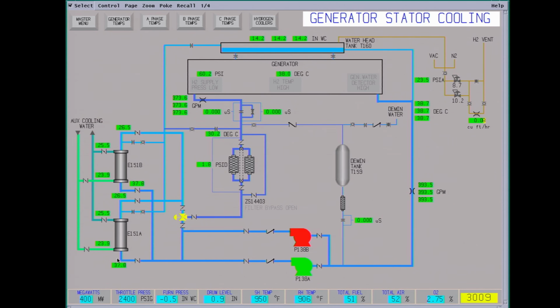We have our auxiliary cooling water, cools heat exchangers. The water in this part is very pure, deionized water, and it goes through resin beds. This water will actually go through the windings in the generator, pull out the heat. This would be a tank on top of the generator, maintains level.